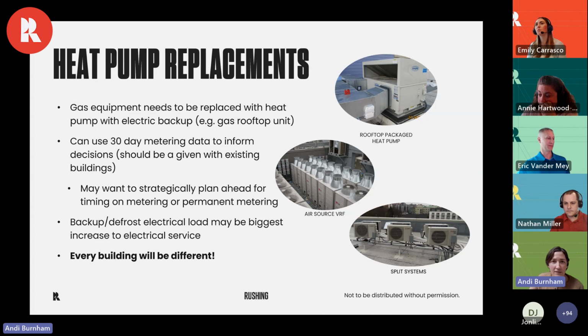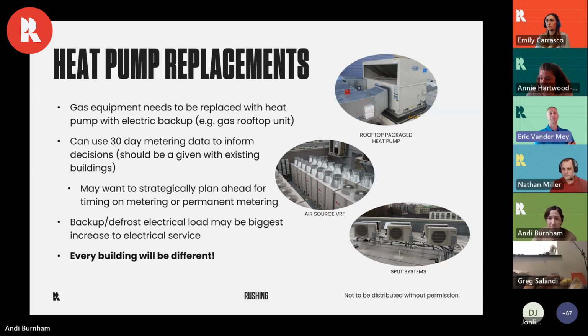Go ahead, Eric. Understanding where you'd want to feed that equipment from, which electrical panels specifically, and getting that metering data is definitely an important step. It takes time to put together a detailed heating load on a lot of these large buildings. Are there upgrades planned? How does that system need to be sized, both from how it's typically operating and on peak winter days, versus how it has to be sized from a code standpoint—these are all things that need to be evaluated.